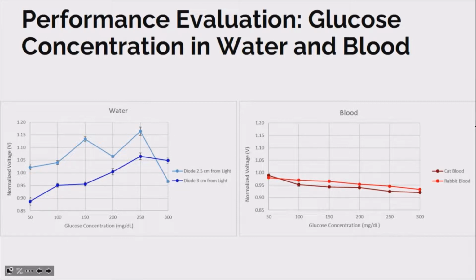The water had a positive trend while the blood had a negative trend, and we attribute this to the water interfering with the LED signal, so it amplified the signal as it was picked up by the photodiode. However, the blood reacted as expected, where the more glucose that was there, the more of the LED light was absorbed, so it reduced the voltage obtained by the photodiode.